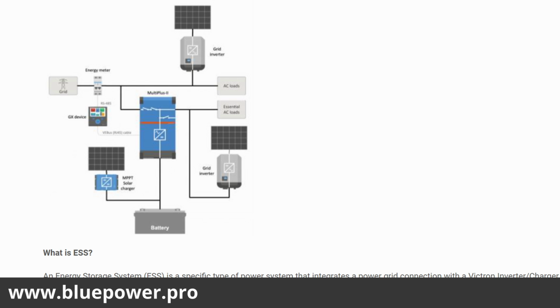So we can have a grid connection running through the energy meter that measures some of our non-essential AC loads. And then on the same line we can install a grid tie inverter that can exceed the capacity of our inverter. So we can have an 8 kilowatt PV inverter on the input and run 5 kilowatts on the output of our 5 kVA inverter. So through the inverter we've got our essential loads connected, and then on the output side, we've got another inverter connected that's AC coupled on the output.